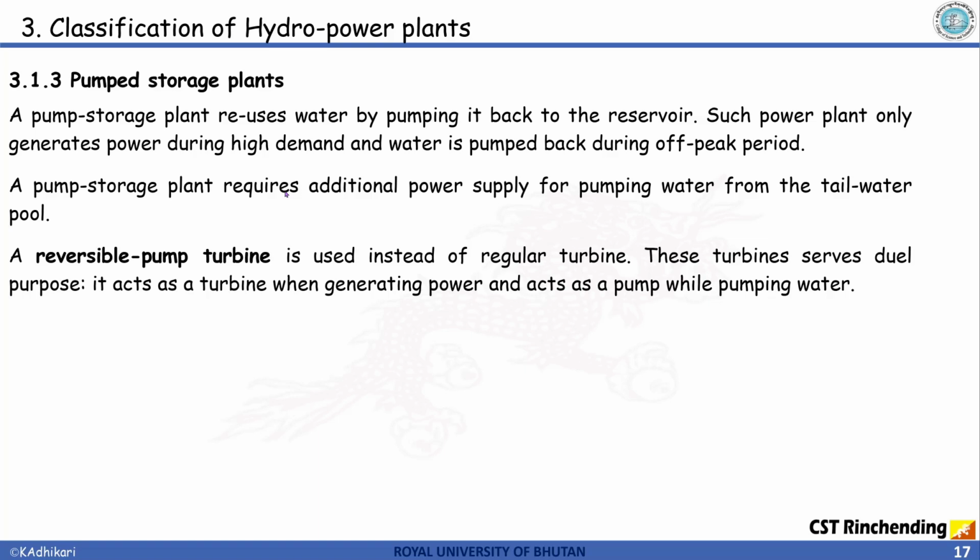So the real advantage is cost. When the power is required and the demand is more, the cost is going to be high, right? When the demand is less, the cost is going to be low. So when the demand is high, we produce energy, and when demand is less, we pump back. The energy spent may or may not be the same, but the cost is drastically less when we pump back, and that pumping has to happen when the demand is low, or else there won't be any profit.